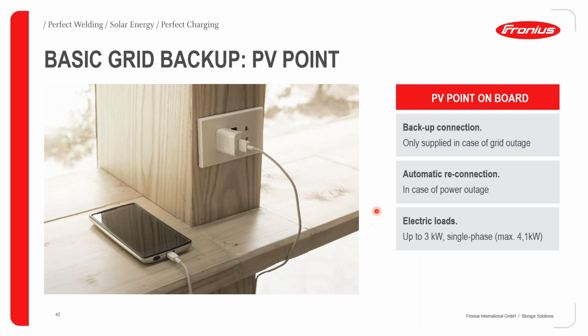In terms of the loads that you can connect to the PV point, the PV point is a maximum of 3 kilowatts in single phase. Also for the three-phase Gen 24 inverters, the maximum that you can get from the PV point is only 3 kilowatts in single phase. And the maximum inrush current that can be supported can constitute a power of up to 4.1 kilowatts for about 5 seconds. This can be quite useful when you're starting things with motors, maybe a fridge or a power tool connected to the PV point. So the PV point is actually very easy to use, and there is no additional installation necessary to be able to harness power from it.